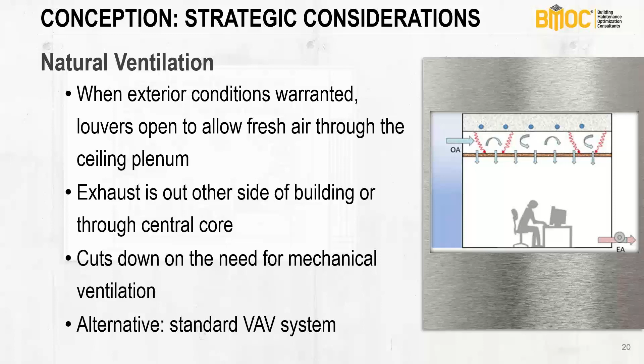So in this system we had 61 variable air volume boxes. This was a VAV system, but it was not traditional. You had 61 variable air volume boxes that required filters because they were your first stage of filtration due to outside air coming in. And those filters require replacement quarterly. And even though they're not on all the time, they needed to be replaced quarterly because above that ceiling, you're accumulating dust. That ceiling tile is eroding and producing dust just over time as it breaks down. And you just have air coming up through the seams and everything. So dust is getting up there even if those louvers aren't on.